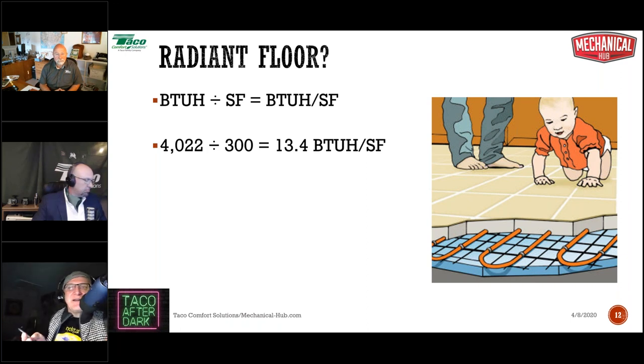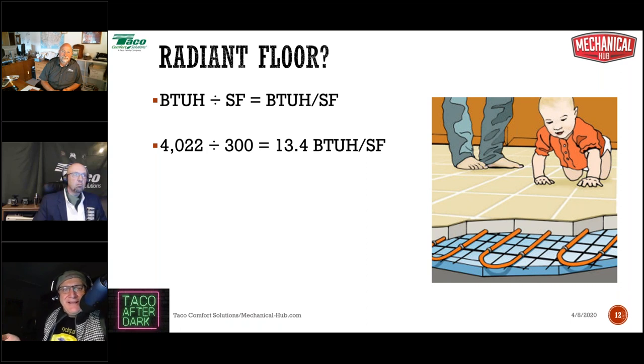It doesn't matter if I can get more. A lot of people say, well, you have to put that in so you can maximize the output, you can get more output this way. I've got to get what I've got to get. If I can get more, it doesn't matter. It's like if everybody obeyed the speed limit, what good is a car that can go over 55 miles an hour? In this case, 13.4 is the speed limit and it's universally enforced. It doesn't matter if I can get 40, who cares? It doesn't make any difference. I only need 13.4 BTUs per square foot in this room.